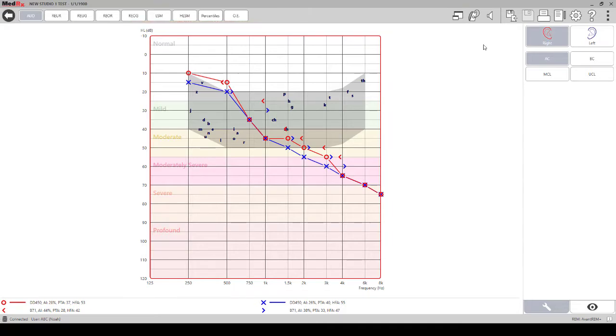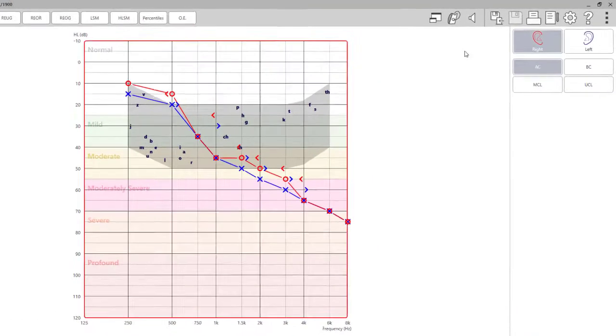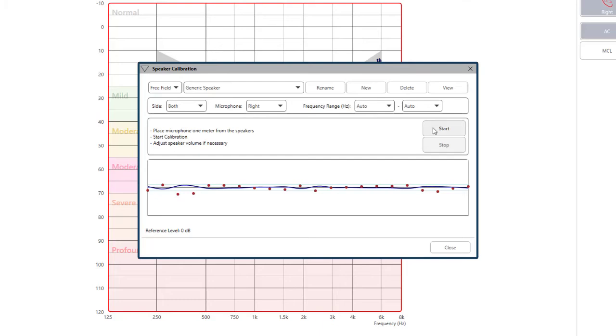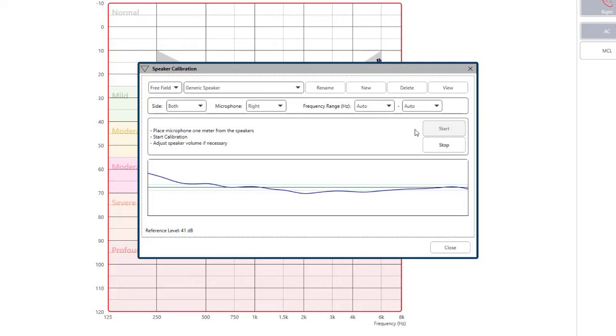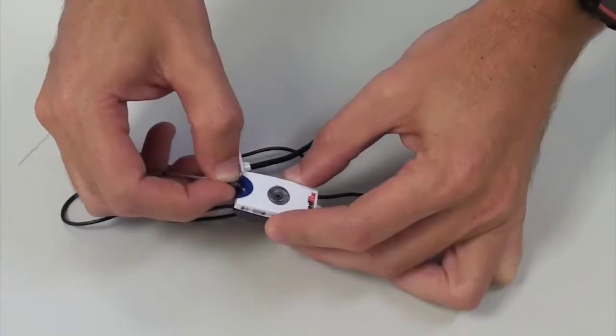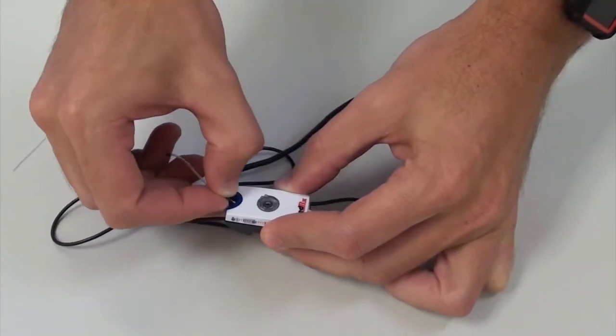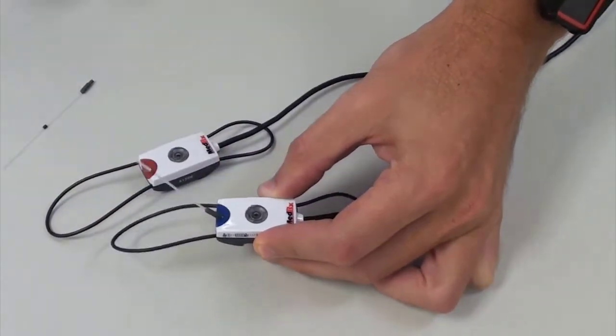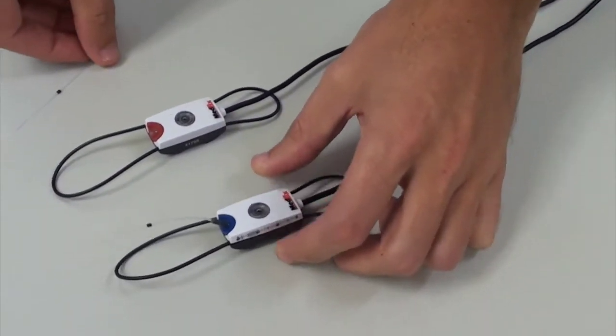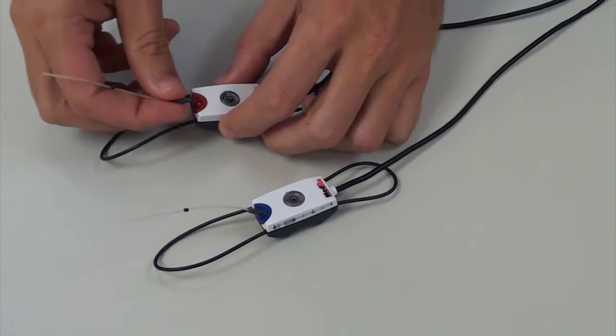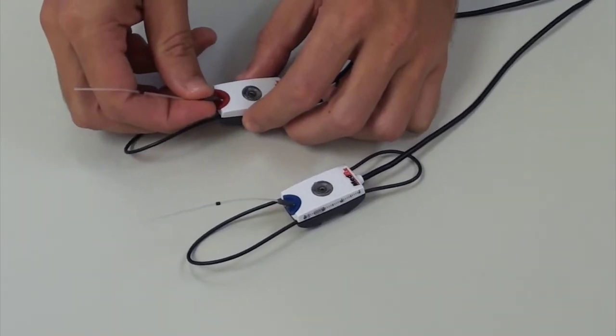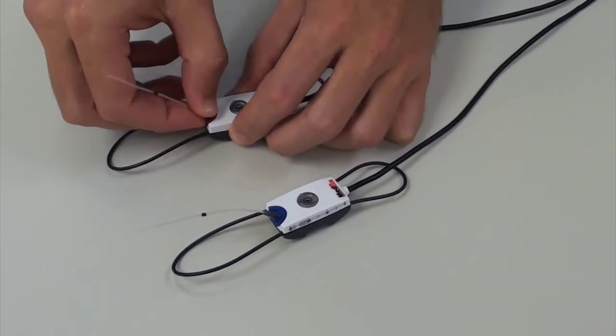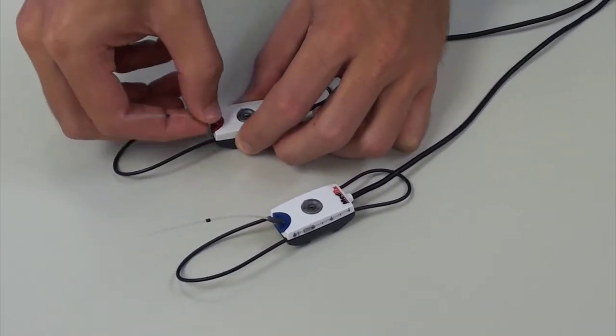To calibrate the speakers, click on the speaker icon at the top of the screen. When you click start you will hear the calibration noise. Make sure to attach the probe tubes to the reference microphones and place them about one meter from the speakers. It is important to not have anything blocking the speakers.